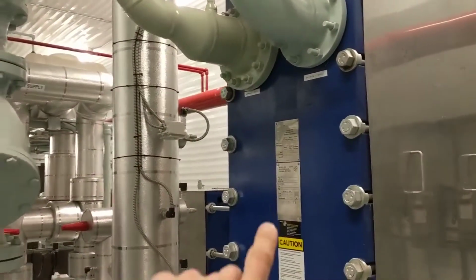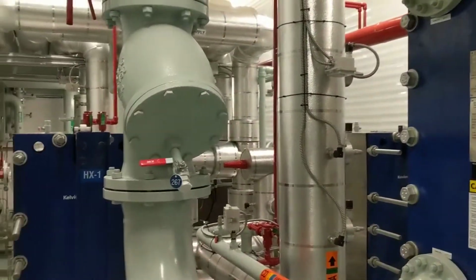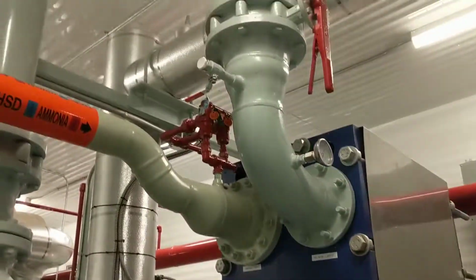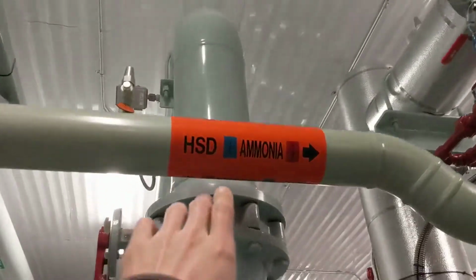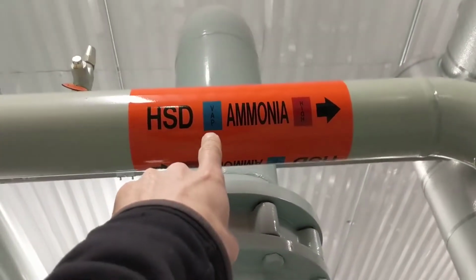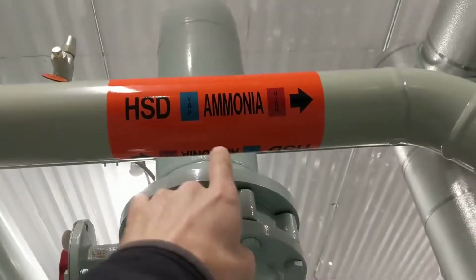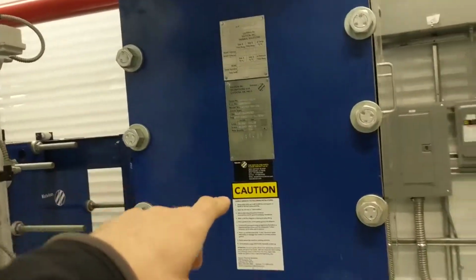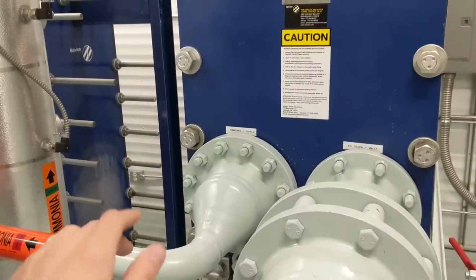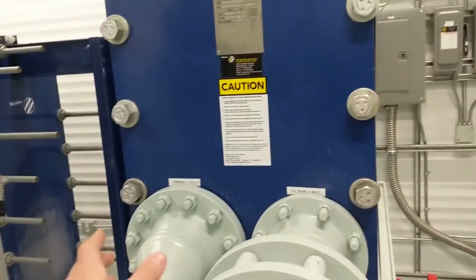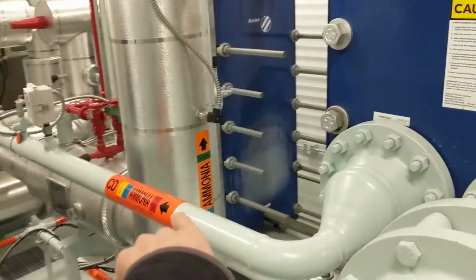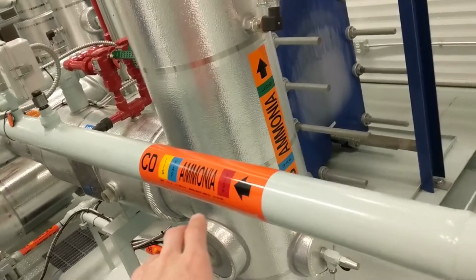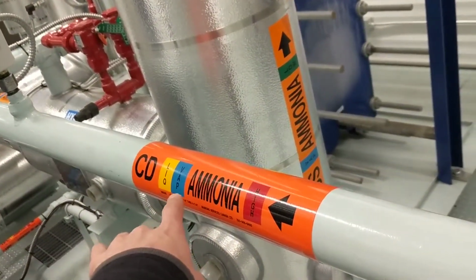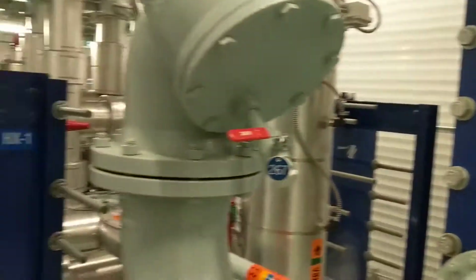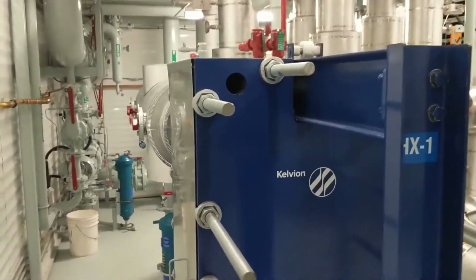I guess I should mention, this one's our ammonia condenser. So it's taking the high pressure, high temperature ammonia, which you can read on all of these labels. This means that it's vapor, that means that it's high pressure, and it's going in, it's condensing using the glycol to cool it off, or I should say remove the heat from it. And then out here you've got potentially a combination of liquid and vapor ammonia, still coming at high pressure. So that's HX3.